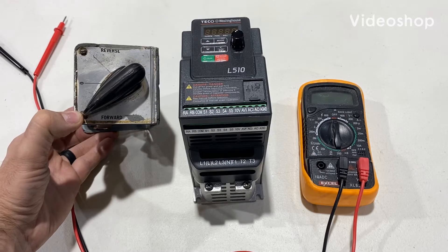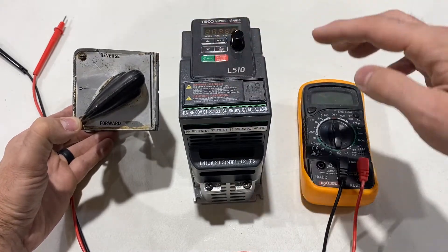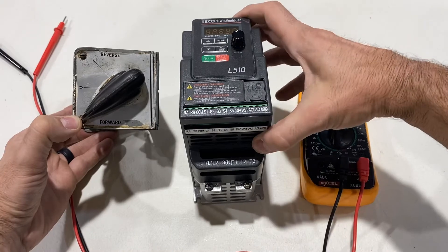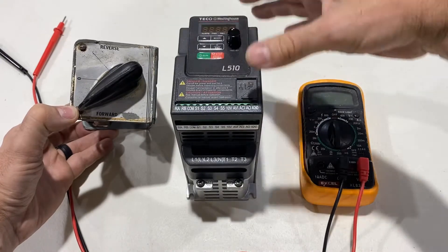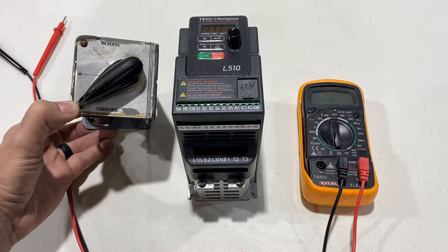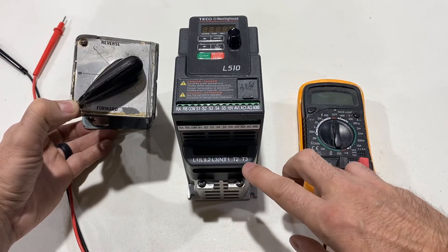In this video I'm going to quickly show you how to set up your existing switch from your milling machine to control forward and reverse on a variable frequency drive. This is a TECO Westinghouse L510, one horsepower — and if you're wondering why it's skinnier than ones you may have seen on YouTube, it's the 240-volt version: input 240-volt single phase, output 240-volt three phase.